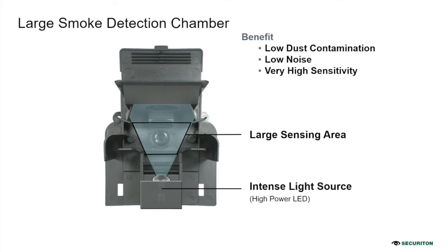As I explained in the question and answer session, the temperature range is as low as -30 to +60 degrees centigrade. So sensors can be used in cold or hot ambience, in hot countries or cold countries, anywhere. MTBF, the mean time between failures or the life of the detector, is more than 10 years, which I think is double the life of other technologies. Then there is less degradation of intensity over time, which results in lower cost of maintenance and operation. And we have IP54 and IP66 models also available.